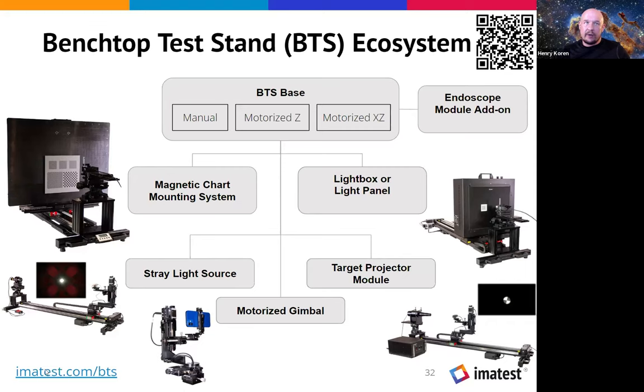And then there's another version of the BTS, which is a stray light and target projector version. I think we've talked about both of those, and they both use the gimbal. They just use different light sources, and you can switch them relatively quickly if you want to test resolution or stray light.